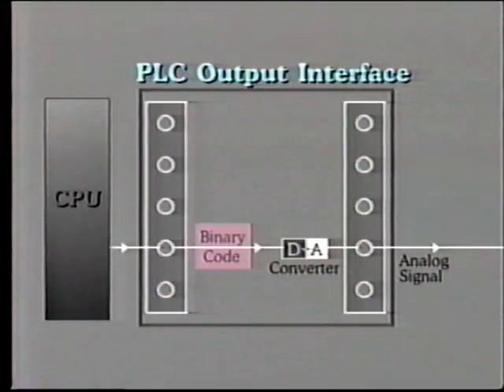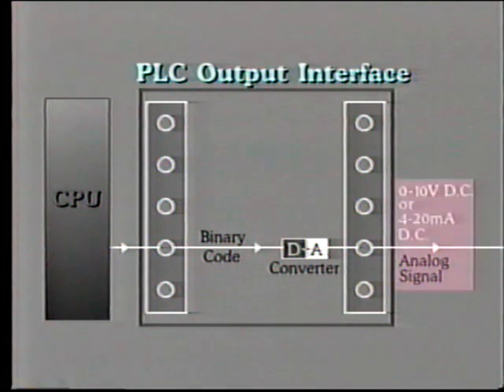The binary output signal from the CPU must be converted to an analog signal. This is performed by a digital to analog converter, which is located in the output module interface. This is just the opposite arrangement to that for handling incoming analog signals. Output analog signals are typically between 0 and 10 volts DC or 4 to 20 milliamps DC.